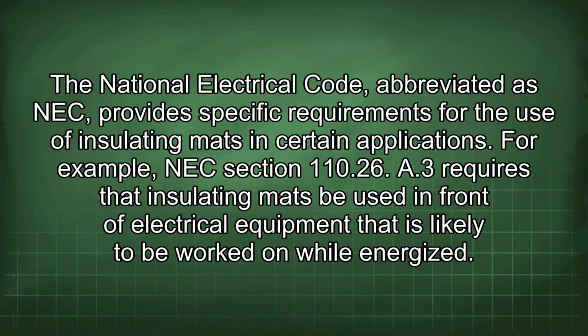The National Electrical Code, abbreviated as NEC, provides specific requirements for the use of insulating mats in certain applications. For example, NEC Section 110.26 A3 requires that insulating mats be used in front of electrical equipment that is likely to be worked on while energized.